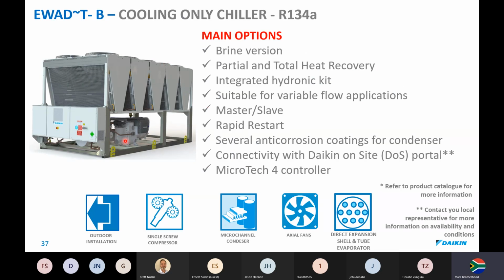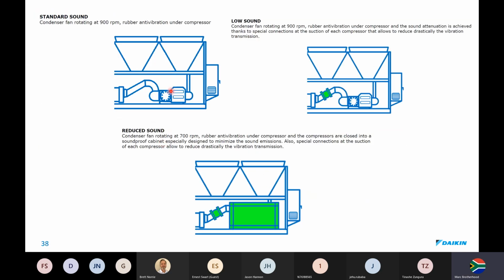Interestingly, on these chillers, when we do the low sound for you, this is pretty much what we do. Because these are screw compressors, we limit the condenser fan RPM to about 900, and we put rubber vibration mounts under the compressors. When we go even quieter, we put an expansion bellows in the refrigerant pipework to stop resonance of the pipe and pulsations through the pipework. And we put this on the suction line.